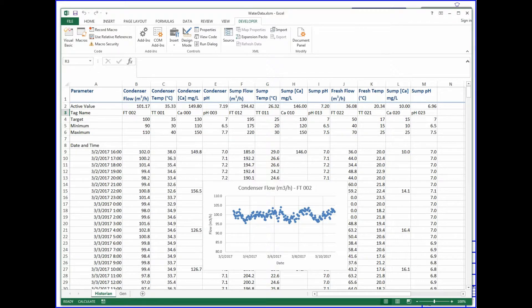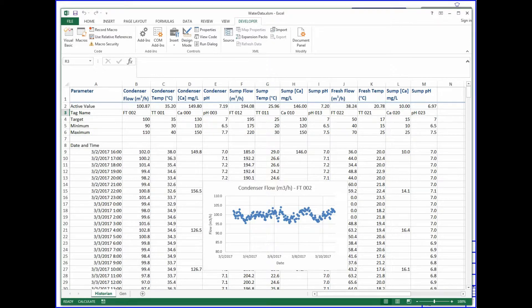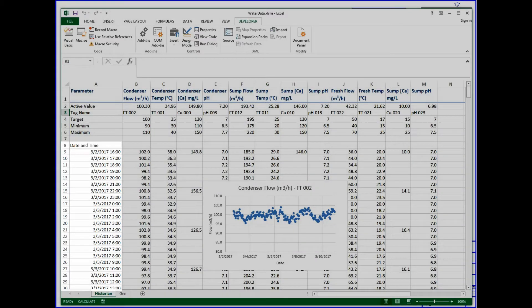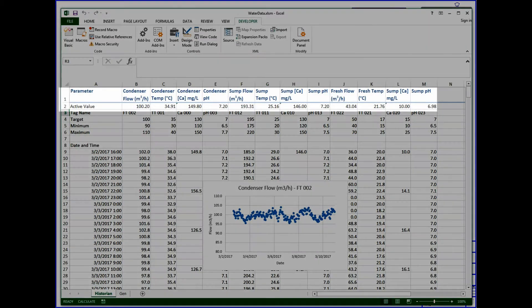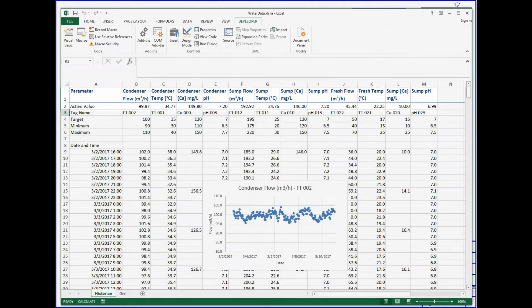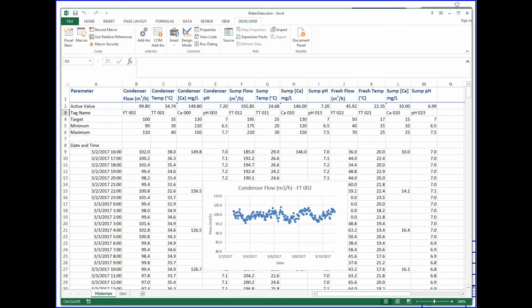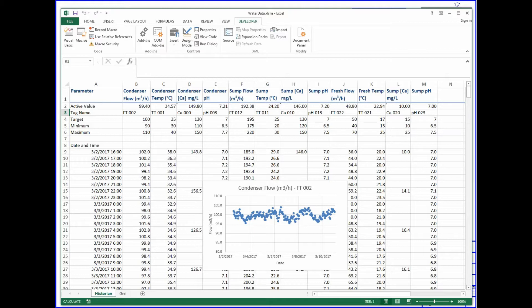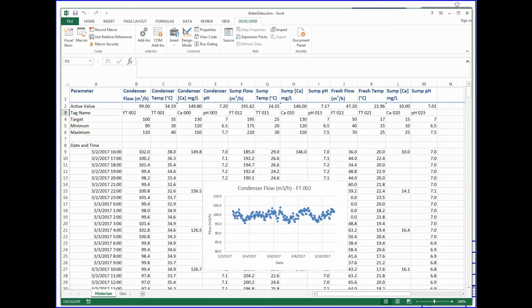I've set up the Excel sheet with data for the temperatures, pH, flows, and calcium concentrations for each of the three streams. Generally, the COM connection updates the Excel sheet with CADSIM's current simulated time and then sends back to CADSIM the sensor values associated with that moment in time. The continuous sensors, the ones for pH, temperature, and flow, have their values reported hourly and I've interpolated between each. However, the calcium assays are reported every six hours and I have these values set to change only when a new value is reported.